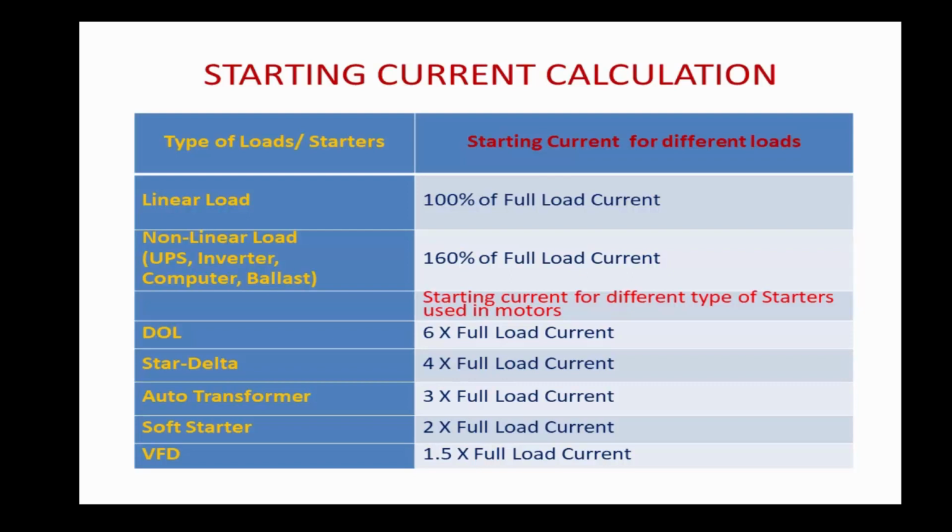If it is a linear load, starting current is probably 100% of full load current. If it is a non-linear load, as per standard, starting current may be chosen as 160% of full load current. If the motor is accompanied with a different type of starter, once again we have to consider full load current as per the starter used in the motor.